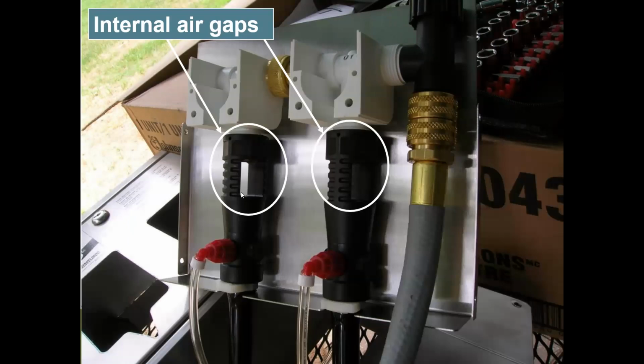It's got these manufactured air gaps included right in it. That is its backflow prevention. It feeds the chemical through the clear little hoses with the red nipples or attachments, where the chemical comes in and is fed through a Venturi effect. The water flowing down the hose is pulling chemical into that water stream.